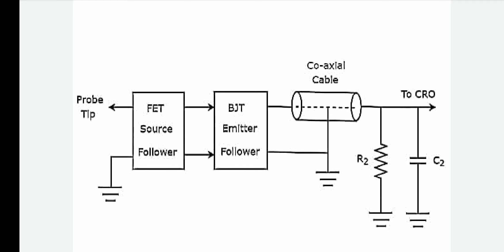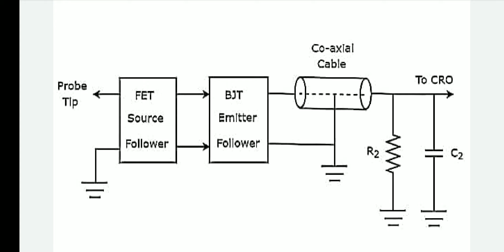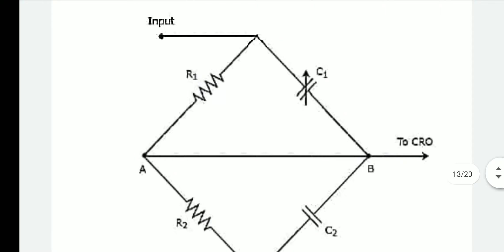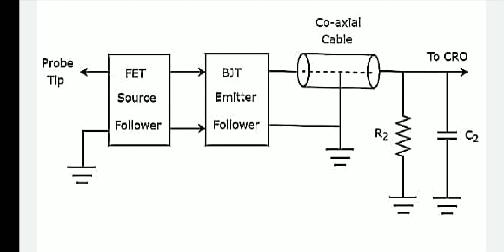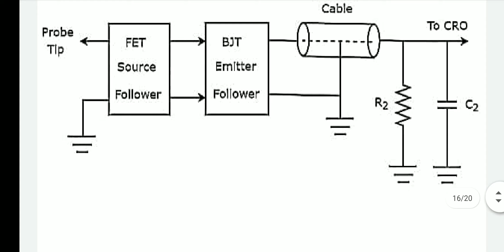In the active voltage probe, on the CRO side the same input resistance, capacitance, and coaxial cable are used. On the other side, the change is at the test circuit side: instead of the simple R1C1 parallel resistance-capacitance circuit, they have chosen an active circuit, an FET source follower and BJT emitter follower. This active circuit effectively increases the input impedance and reduces the input capacitance compared to the passive circuit. That's why it is called the active probe.